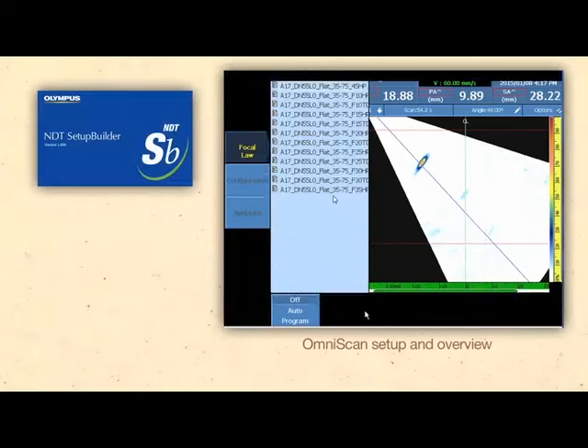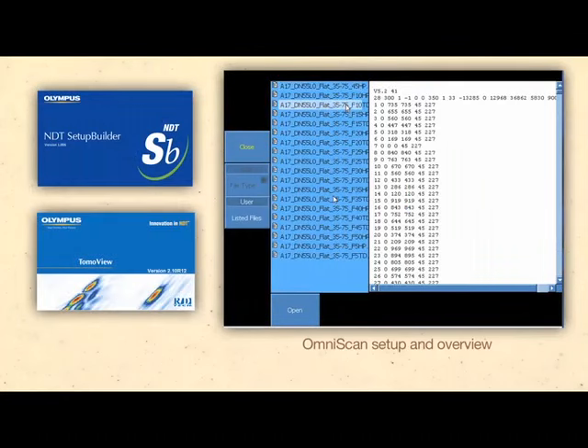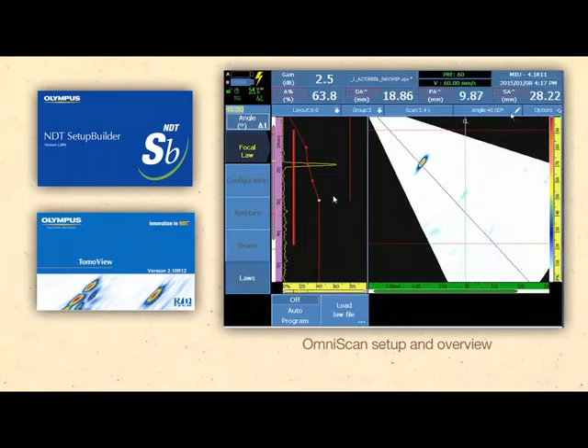Law files are imported from either the Olympus Setup Builder, TomoView Calculator, or library of predefined law files for S-Scan configuration to include angular range and focus.